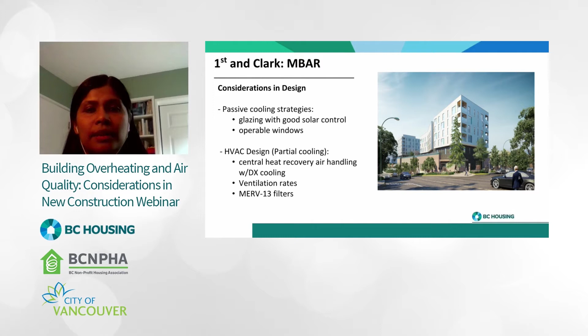So the lessons learned, considering the microclimate conditions, overheating in residential is a serious problem, and the effectiveness of the passive approach is good, but it may not be as effective as we have been thinking in the step code. So a form of active cooling, either partial or full cooling, shall be provided. To keep that in mind, in the BC Housing Design Guidelines 2019, we require all projects to meet the overheating threshold below 20. And you can see the highlighted red ones in the slide, that there are some changes that we bring forward in our design guidelines in 2019.